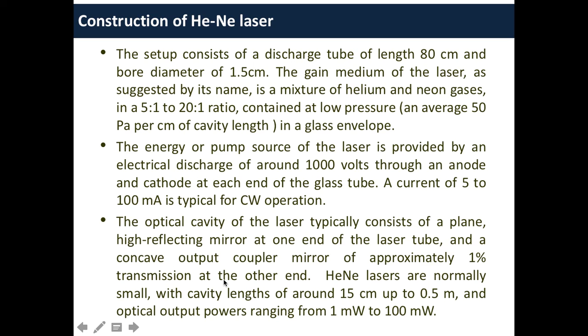The optical cavity of the laser typically consists of a plane high reflecting mirror at one end of the laser tube and a concave output coupler mirror, whose transmission is approximately 1%, at the other end. The helium-neon lasers are normally small, with a cavity length of about 15 centimeters up to 0.5 meter, and the optical output power ranging from 1 milliwatt to 100 milliwatt.